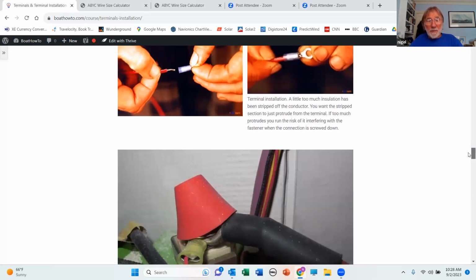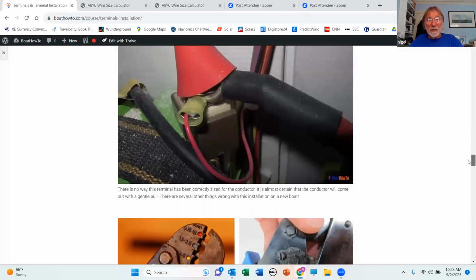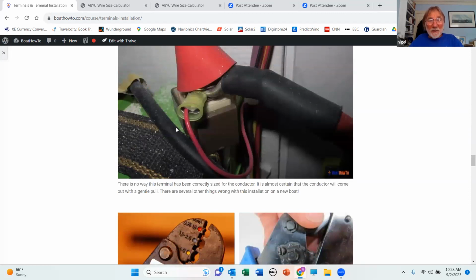And then we want the right crimping tools. And here, this is a brand new boat, by the way. Look at this crimp here. We can see for a start that it's way oversized for the terminal and for the conductor. And then whoever did it didn't have the right tools, so they just mashed it down with a pair of pliers or something. I bet you if I tugged on that, it would come straight out of there.